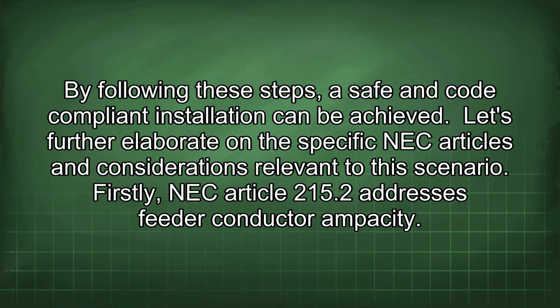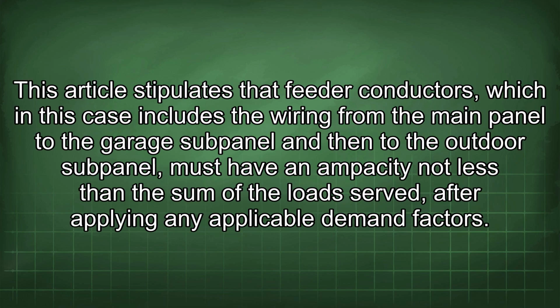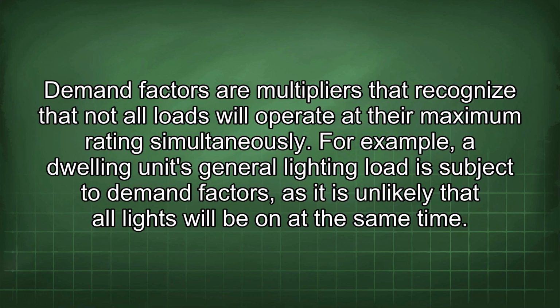Firstly, NEC Article 215.2 addresses feeder conductor ampacity. This article stipulates that feeder conductors, which in this case includes the wiring from the main panel to the garage subpanel and then to the outdoor subpanel, must have an ampacity not less than the sum of the loads served, after applying any applicable demand factors. Demand factors are multipliers that recognize that not all loads will operate at the maximum rating simultaneously. For example, a dwelling unit's general lighting load is subject to demand factors, as it is unlikely that all lights will be on at the same time.